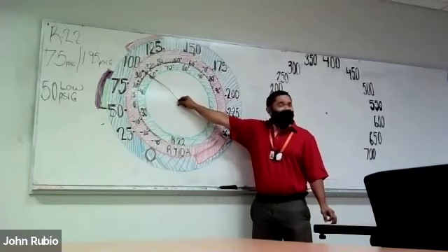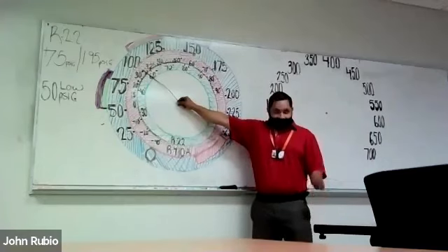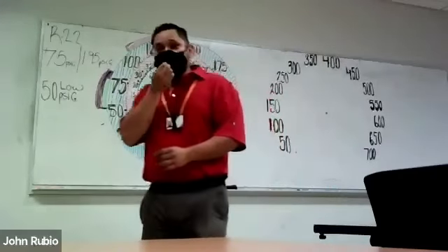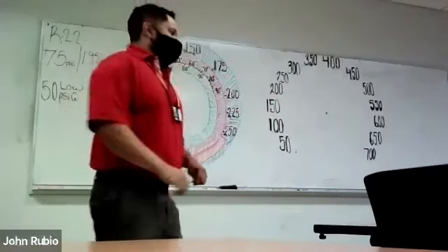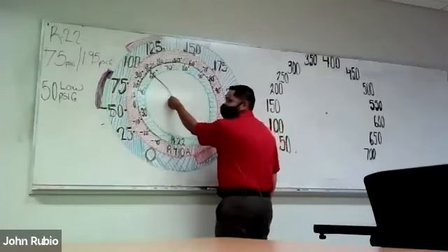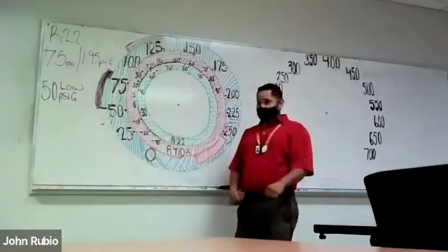It's not, I think it's going to freeze up. It's not hot today, it shouldn't freeze up. It is going to freeze up. When I say predict what an air conditioner is going to do, you cannot leave pressures this low. Or if you are right at the threshold, you have to explain it to the homeowner, show them.